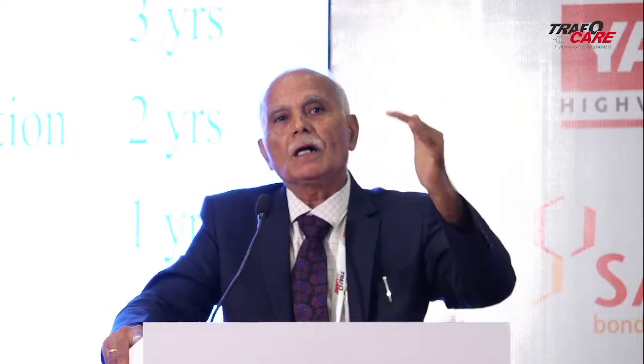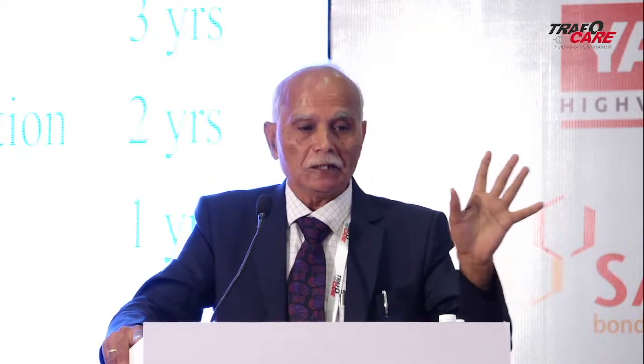So here are the limiting values that we have arrived at for the Indian conditions. Please note that ours is a tropical country. Our ambient conditions are entirely different from the European countries. Say for example, 20 degrees is their ambient condition, whereas we can go right from 20 degrees to 45 degrees. So our electrical equipment will be facing much higher thermal stress. Our degradation levels will be much higher. So we have to look into these aspects in a careful way and decide what will be our limiting values as compared to the Europeans.